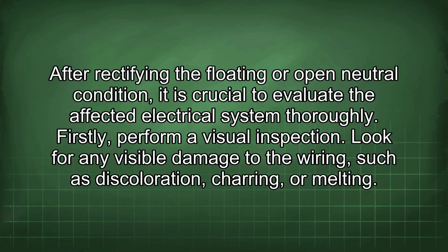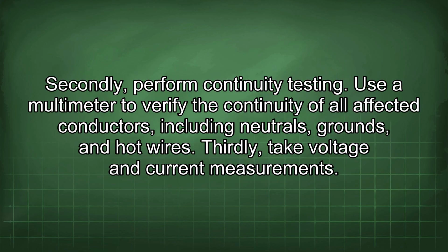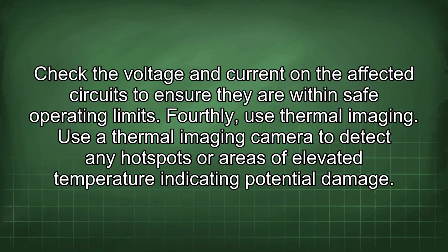Firstly, perform a visual inspection. Look for any visible damage to the wiring, such as discoloration, charring, or melting. Secondly, perform continuity testing. Use a multimeter to verify the continuity of all affected conductors, including neutrals, grounds, and hot wires. Thirdly, take voltage and current measurements. Check the voltage and current on the affected circuits to ensure they are within safe operating limits.